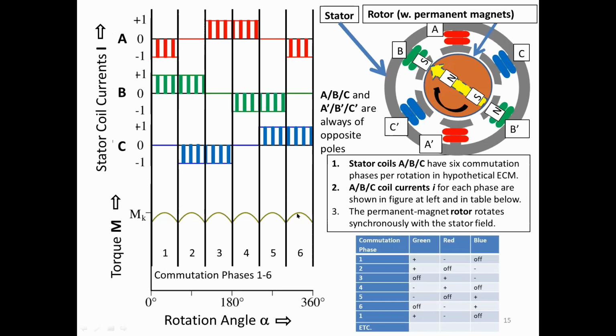And so you have what are called 6 commutation phases. In effect, the rotor rotates through 6 different positions of the magnetic field. The positions of the magnetic field are also shown in the table in the bottom right. Green is positive, negative, or off during commutation phase 1. Green is positive, red is negative, blue is off. During the second position of the rotor, the green coil is activated, the red coil is off, and the blue coil is negative. And this shows the theoretical moment of torque, which has a bit of ripple in it. I'm going to go back to that point. But this is how ECMs work.